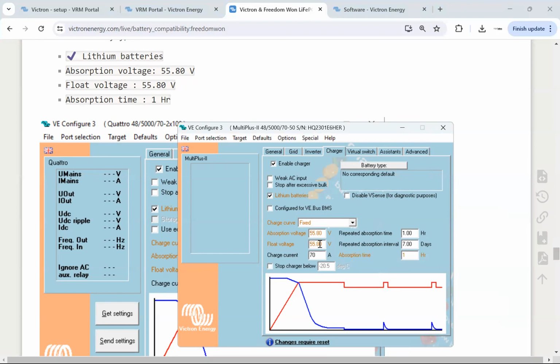Now, just so you know, these settings are only applicable if the BMS gets disconnected from the Victron system. Otherwise, these settings will be overridden by the data that's coming from the battery BMS. There is one other application where these settings actually make a difference, and that is when you've got AC coupled solar and at frequency shifts. The frequency shift will happen based on the absorb and the float voltages.